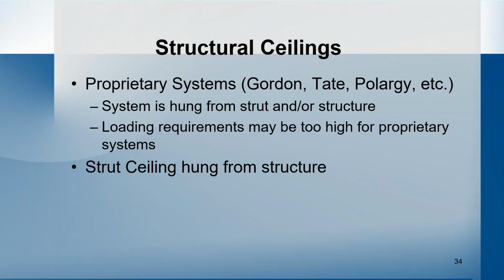So the different types, you have either a proprietary structural ceiling system, so that could be like Gordon, Tate, Polargy, there's some others out there. So that system is either hung from an interstitial strut that's supported by the structure, or the ceiling itself is just directly supported from the structure. Some of the loading requirements for the project may be too high for these systems. And so when that happens, then you have to get into a strut ceiling system. And so then that strut ceiling system, again, is typically hung from the structure or maybe needed to be hung from an interstitial strut as well.